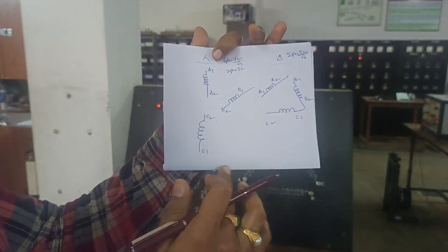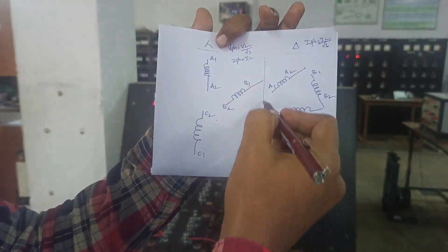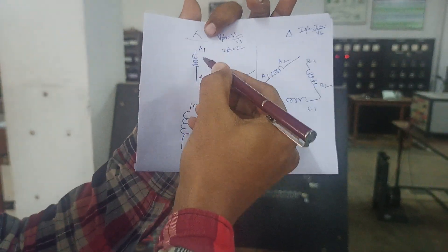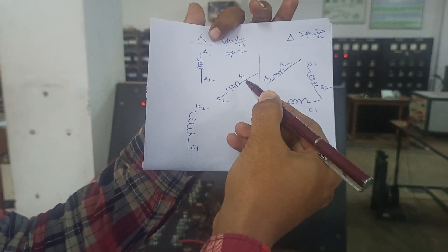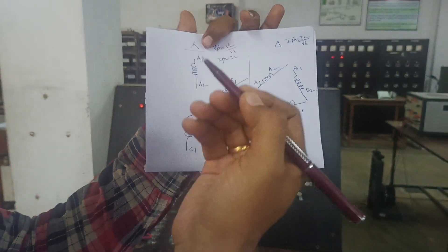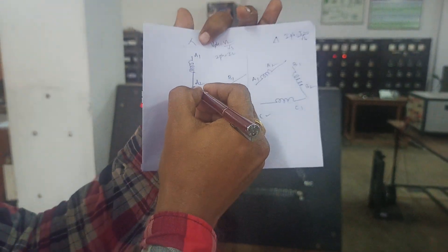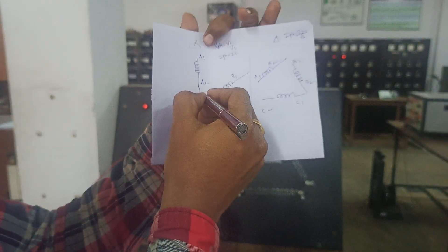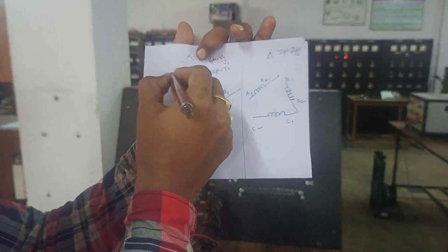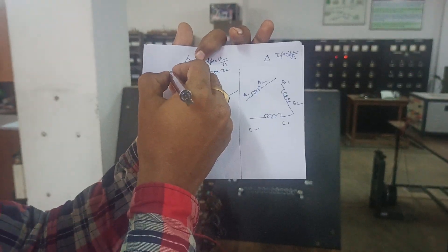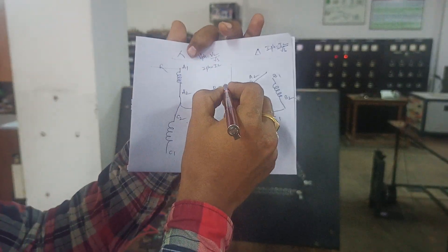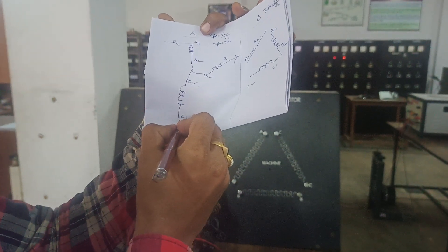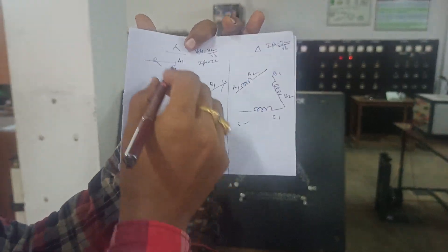I want to connect these three windings in star connection. You see the terminals A1, A2, B1, B2, C1, C2. If you join all second terminals A2, B2, C2, then A1 will act as R phase, B1 will act as Y phase, and C1 will act as B phase.